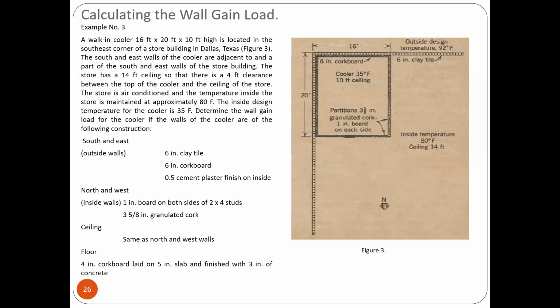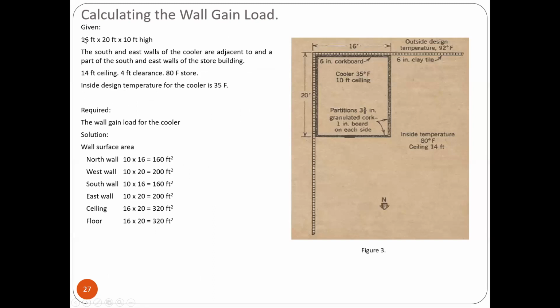South and east, outside walls, meron tayong 6-inch clay tile, 6-inch corkboard, 0.5 cement plaster, finish on inside. Inch yan. North and west are inside walls with 1-inch board on both sides of 2x4 studs, 3 and 5/8-inch granulated cork. Ceiling, same as north and west wall. Floor, 4-inch corkboard laid on 5-inch slab and finished with 3-inch concrete. Yung side niya. So, cubes na siya, di ba? O box. Given niya ito, 16 feet by 20 feet by 10 feet high. Southeast, the south and east wall of the cooler are adjacent to a part of south and east wall of the store building. 14 feet ceiling, 4 feet clearance, 80 Fahrenheit store. Inside design temperature for the cooler is 35 Fahrenheit. So ito yun.